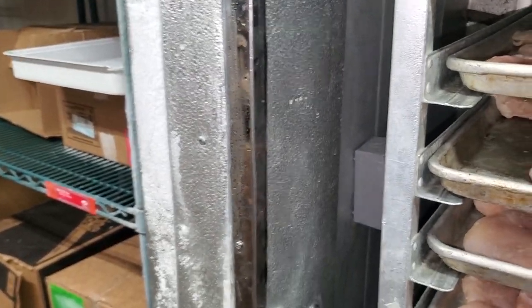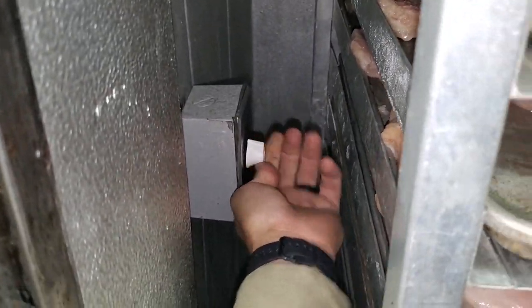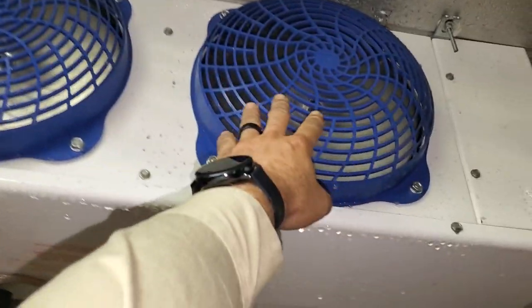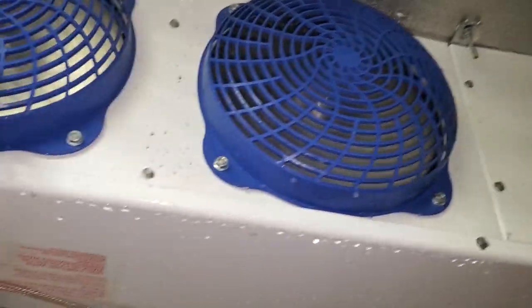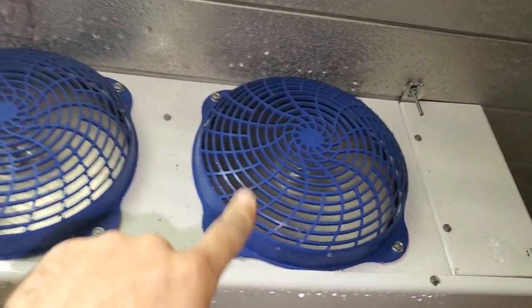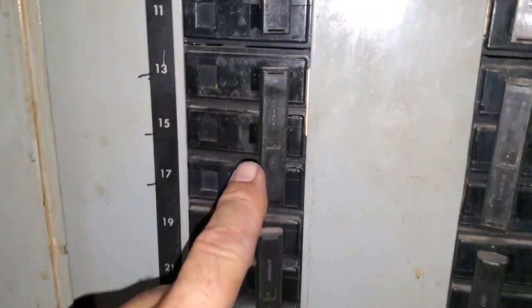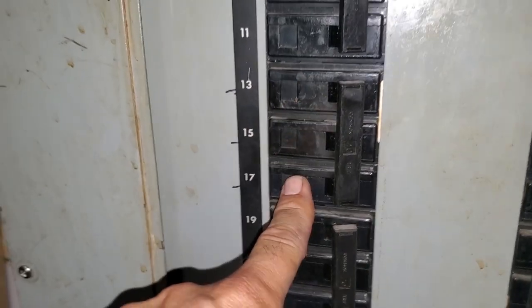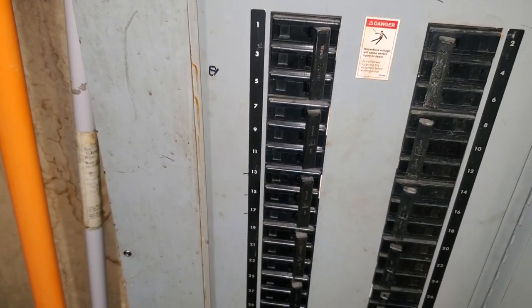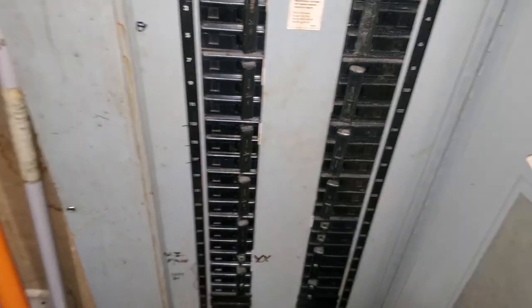Check it out — they were actually doing their job. When they opened the door, someone twisted the twist timer. This thing still has a vibration to it. We're going to have to put a new blade on this one. I don't have it with me, but we'll send someone back out here. That will give me an opportunity to let it run through the day and follow up on it. This is a 40 amp breaker — 13, 15, 17 is the walk-in freezer. It's not getting hot. I don't understand why it was tripped and not blowing the fuses. Time will tell; we'll come back and change that fan blade.